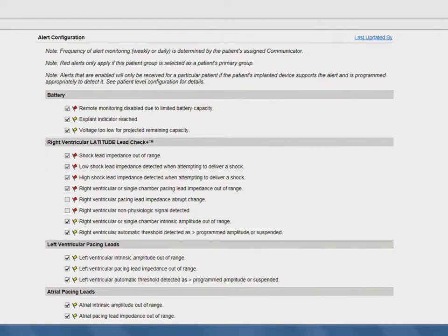Yellow alerts can be configured on or off individually or at the patient group level, based on your clinic's preference, and in some cases the limits or values are customizable. It's important to ensure that each patient's alert configuration is appropriate when the patient is enrolled, as well as when or if a patient receives a new implanted device. Alert notifications are not intended to be used as the sole basis for making decisions about patient medical care. Rather, alerts can serve as prompts to review additional supporting diagnostic information to investigate the alert condition.